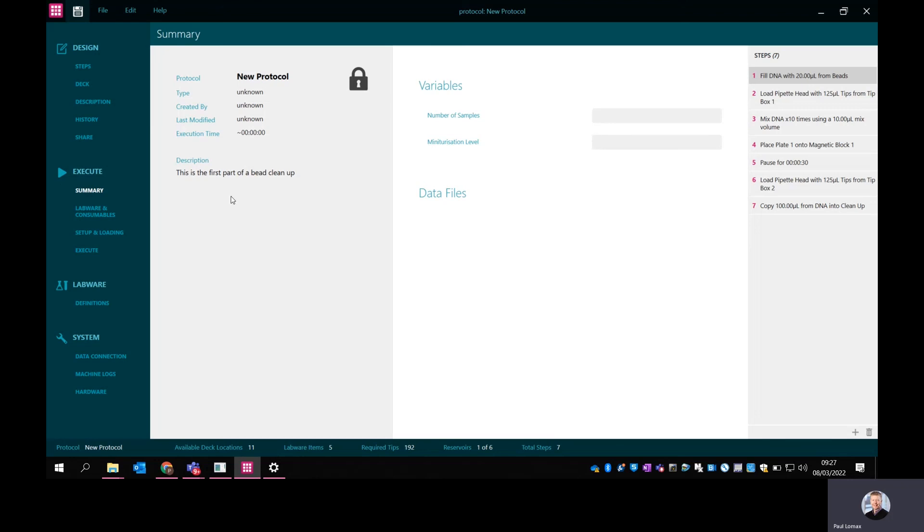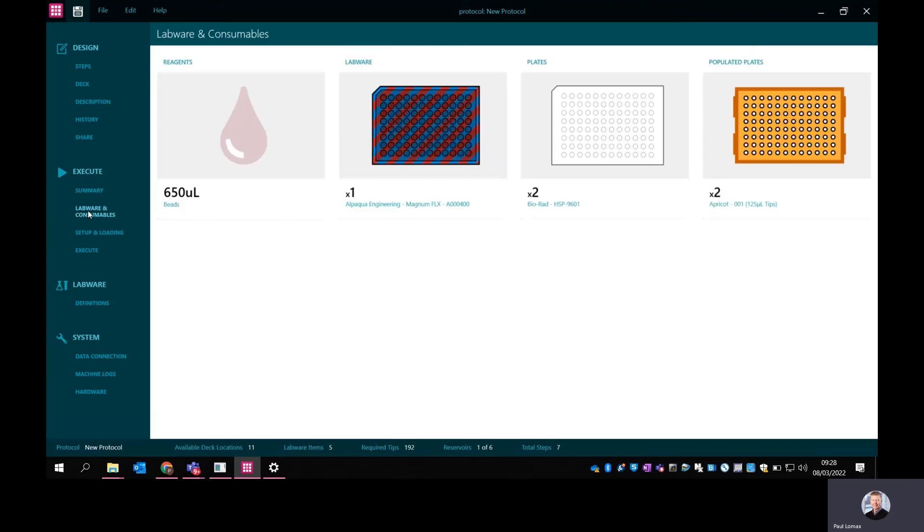A user just running a protocol would see this with some description. If there are any variables they could enter them, and can also see the full range of steps that are in the protocol. They then get a list of labware and consumables required. So they get the calculated volume of what they're going to need in terms of reagents, what labware in terms of things like magnetic plates, what plates they need and how many tips. So they get a shopping list essentially of what's going to be required for the protocol that they could look into the day before just to make sure you've got what you need available in the fridge and in the lab.